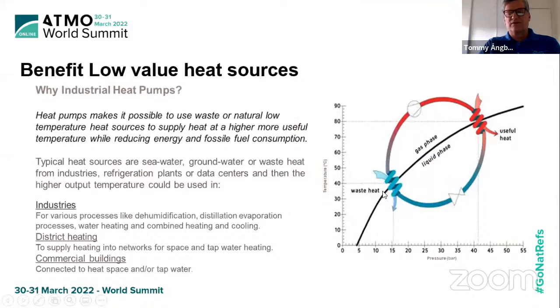Sorry for that. We'll use Fahrenheit, but on this sketch we have Celsius. Well, we are at 40 degrees, and we can have an output of 80 degrees hot water, which is much more useful. And that means also that your pressure in the system will increase on the refrigerant side from around 15 bar to 40 bar, or here we talk about 600 psi in this case, if you take American units. So we are talking about relatively high pressures on the hot side to obtain the temperature we want.